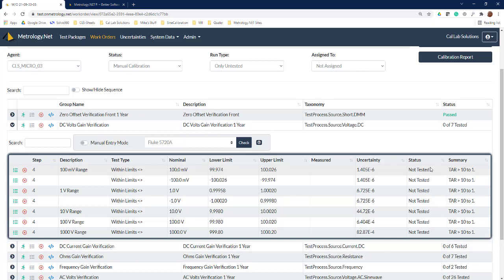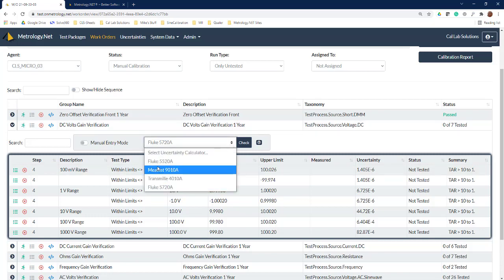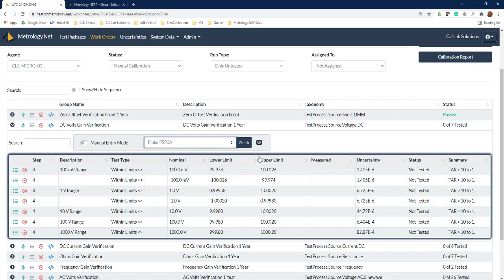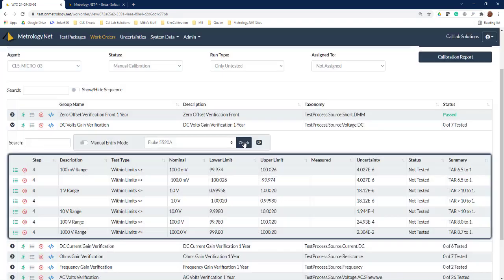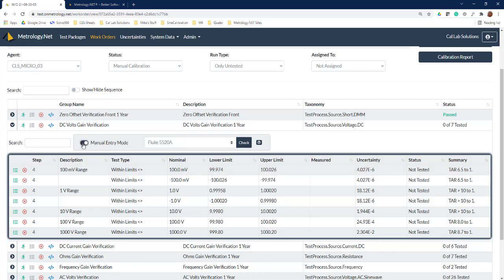We can see we can do this with a 5720. Now let's say we want to check if we can do it with a 5520, so we do the same thing, hit check. Now you can see it's going to go back in and check all those measurement uncertainties, and we're going to see 6.5 to 1—good enough to do this calibration.